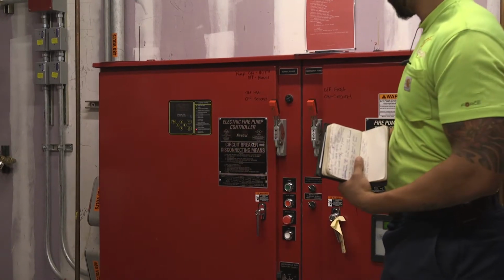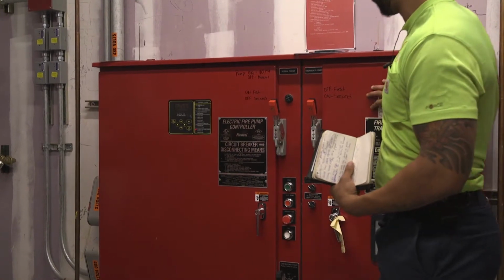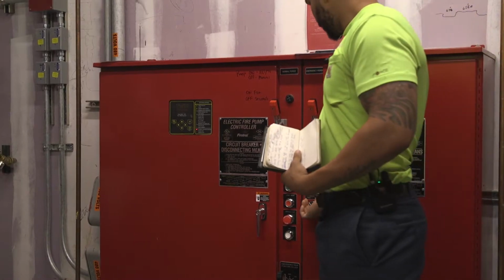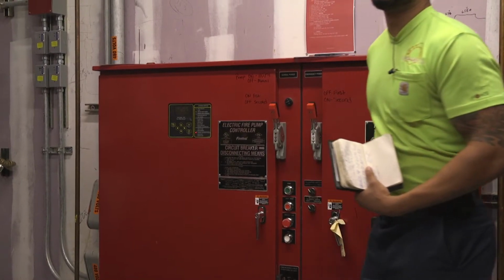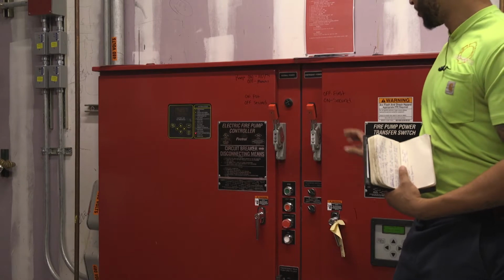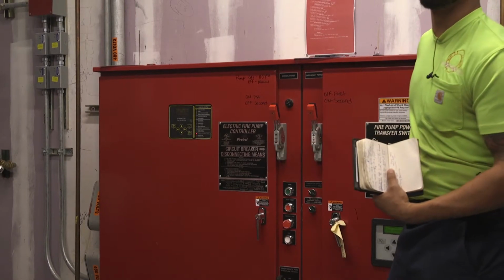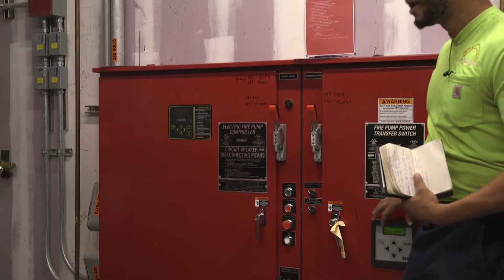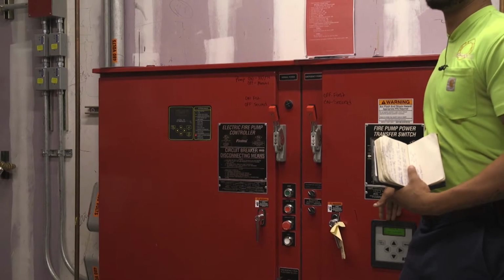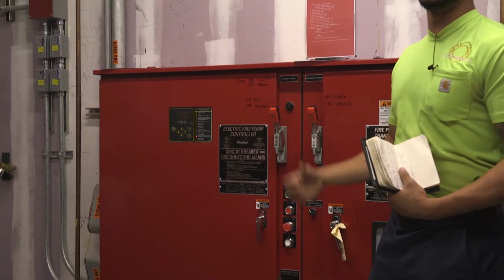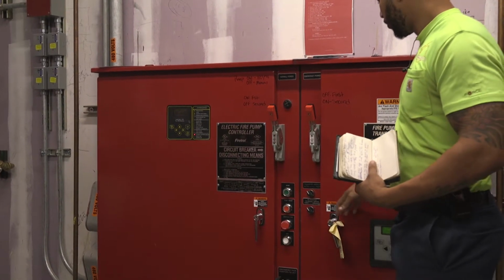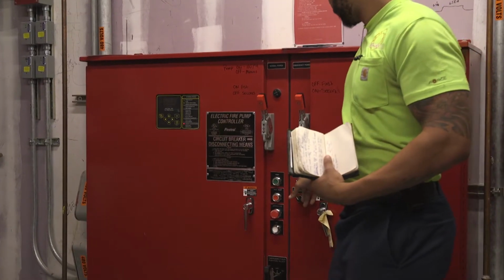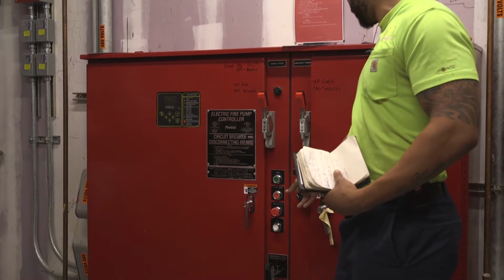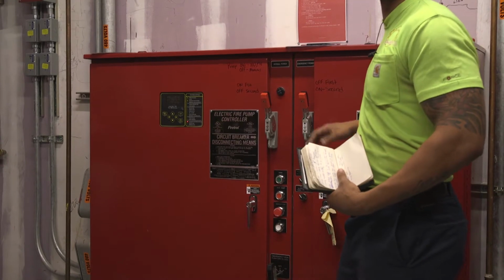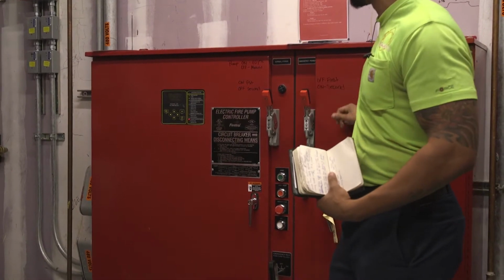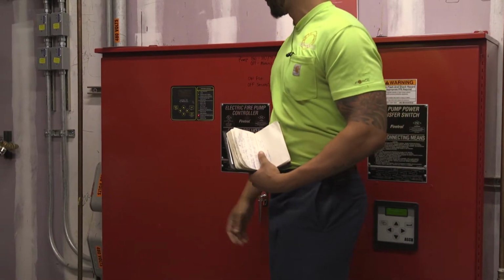Now, this second switch down here is for our timed and immediate transfer. After we transfer from normal to emergency, we're going to want to transfer back. The controller is at its factory setting. It's going to take 30 minutes to transfer back to normal power after it's been put into emergency power, and there's a 5-minute timer on the ATS switch itself. If you want to switch it immediately, you hold this switch here about 10 seconds, and that contactor is going to switch over, and you'll go back from emergency to normal power.